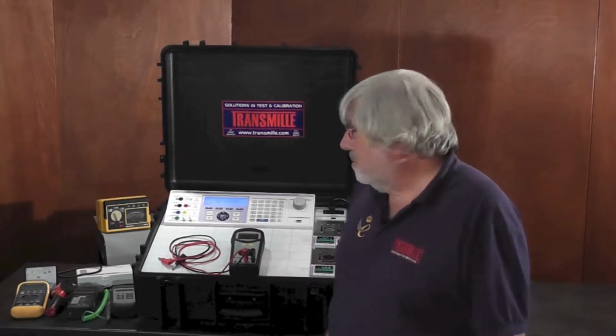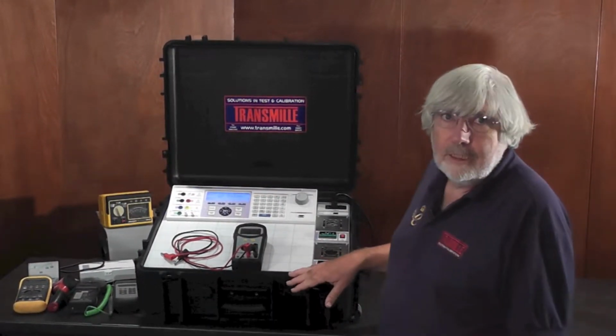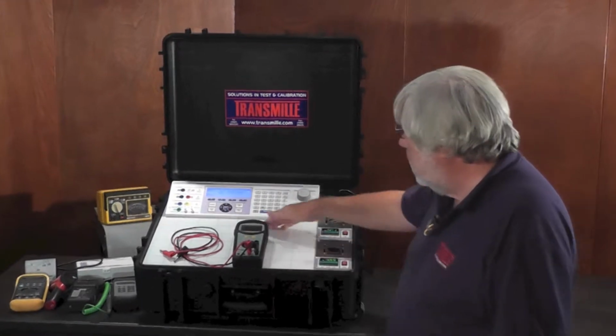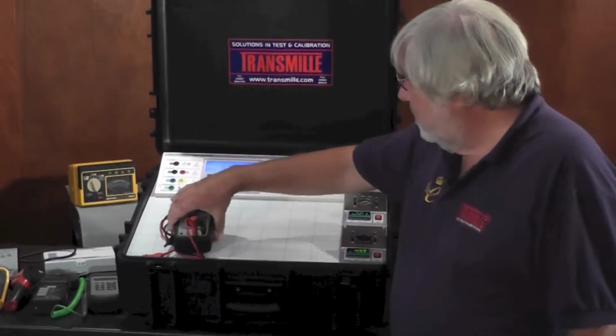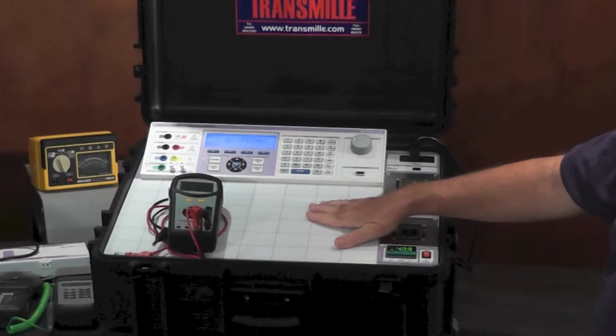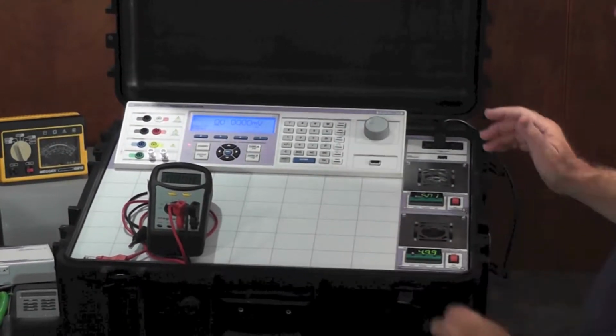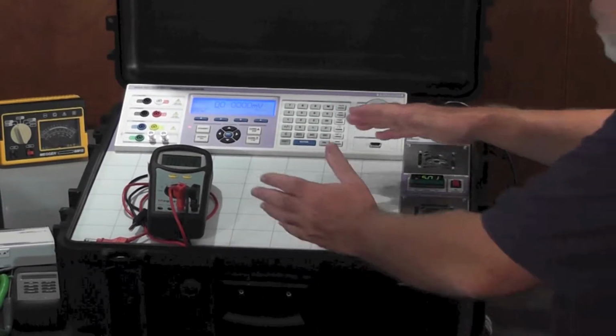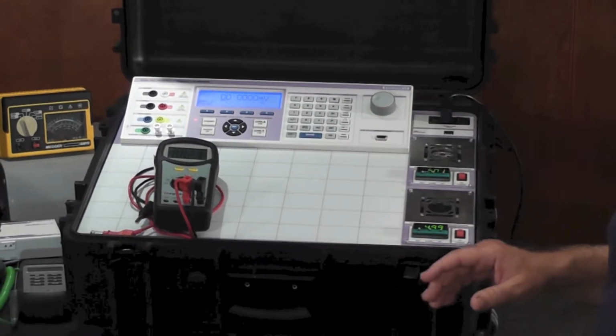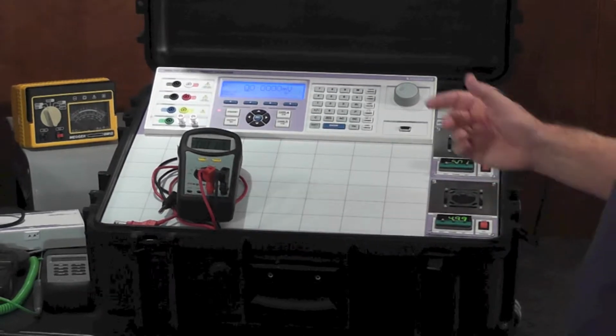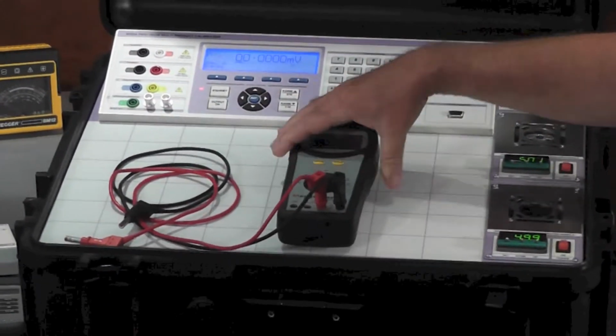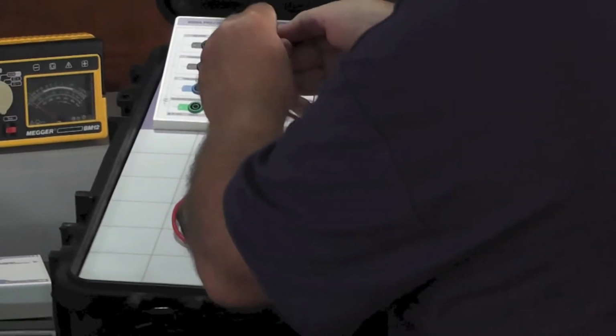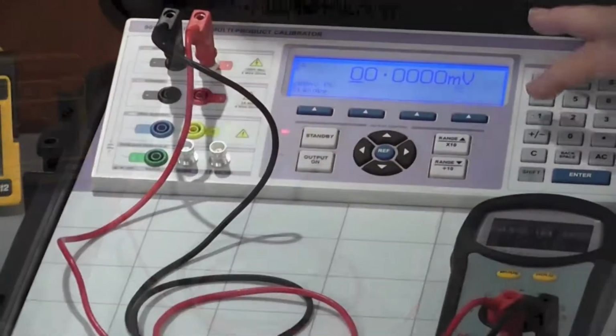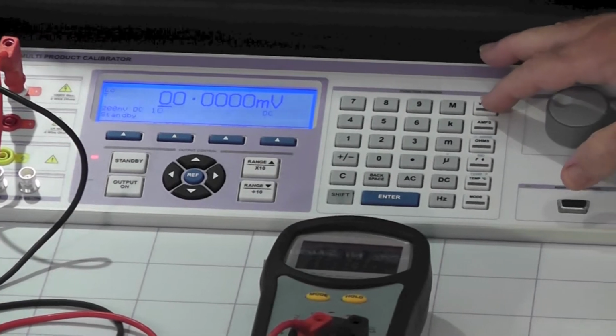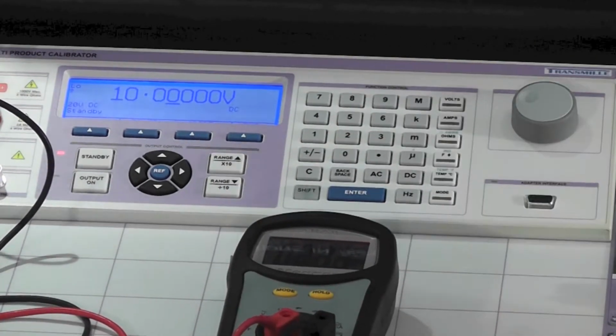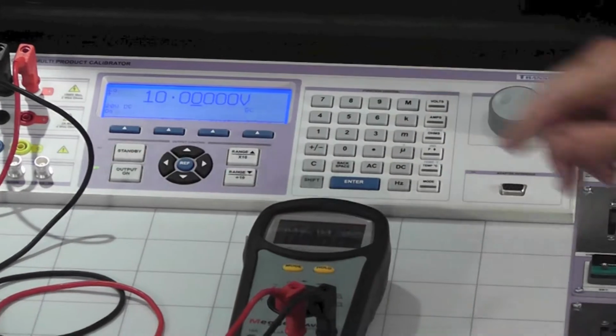The 9000A has been designed to be really simple and easy to use. As you can see here, we have a work platform. Often when you go on site, there's little room to work. So once you've put down the 9000A, you've got your work table to start work on immediately as you open the lid. So to calibrate a multimeter, just connect to the terminals of the calibrator, key in on the digital keypad the voltage you require, I've added 10 volts, and turn the output on.